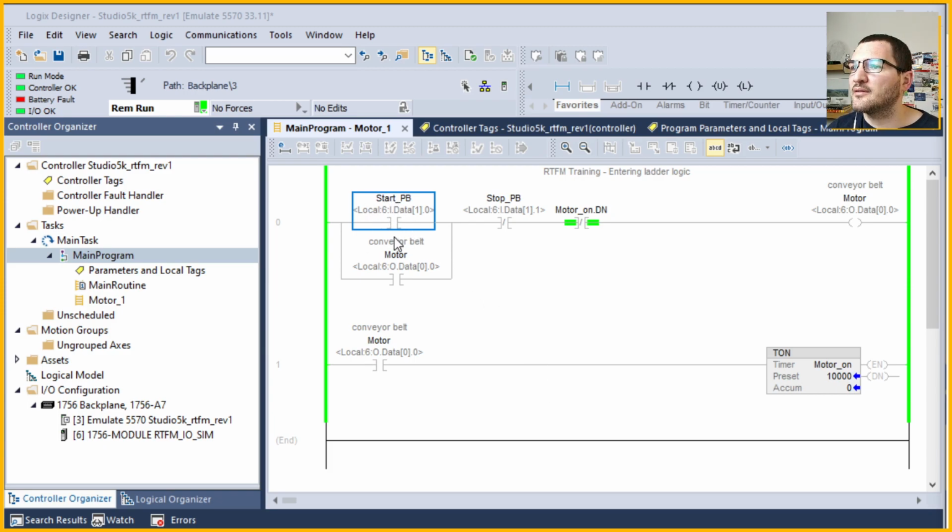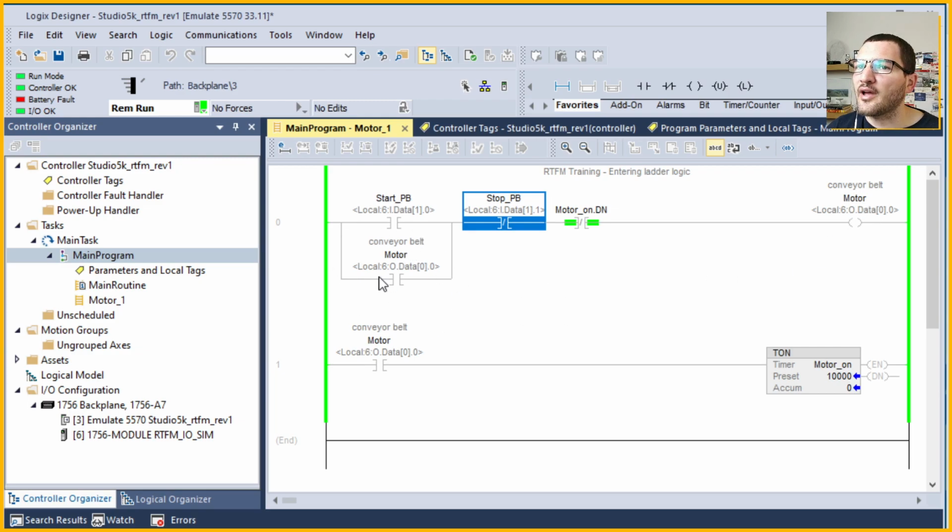You have a start button with a normally open button, and as soon as your contactor is on, its auxiliary contact latches up. Then your momentary push button is released, but your motor stays on because your auxiliary contact takes over. If you're an electrician, I'm sure you know that.